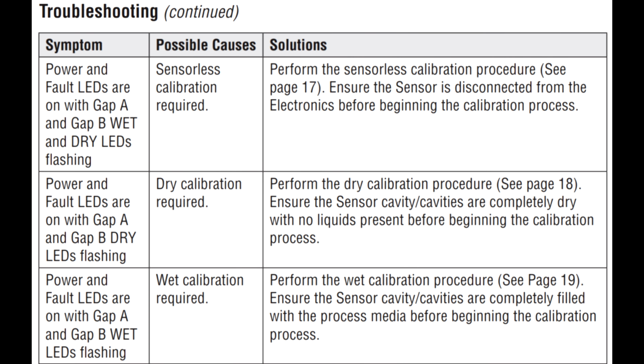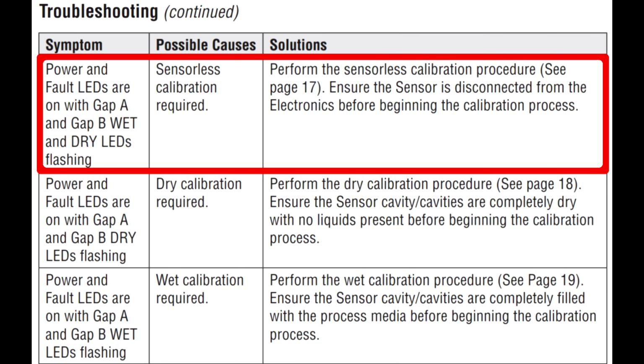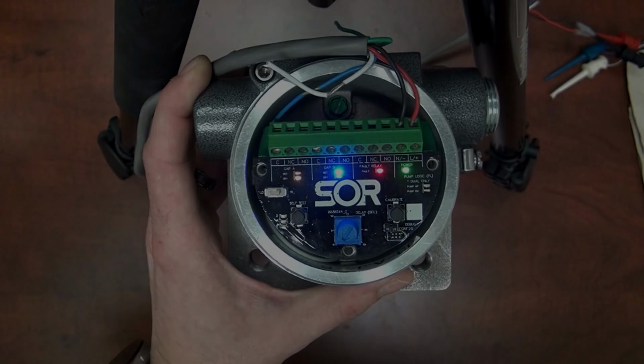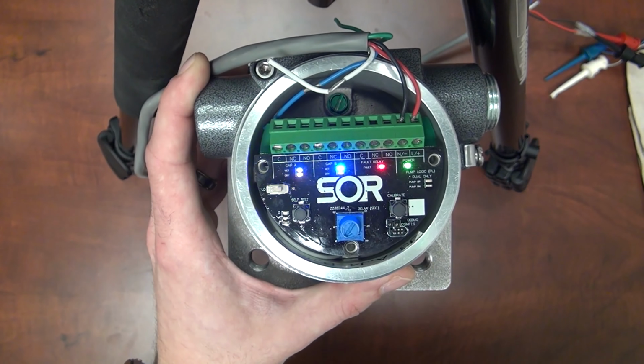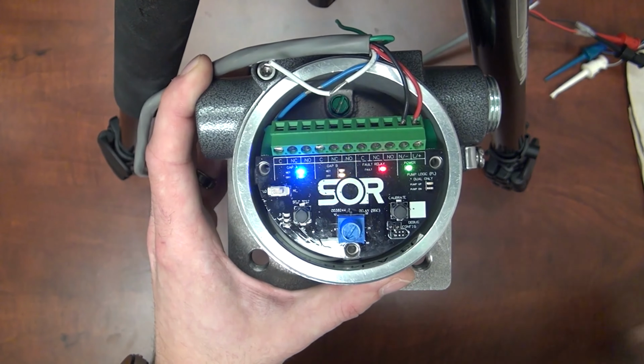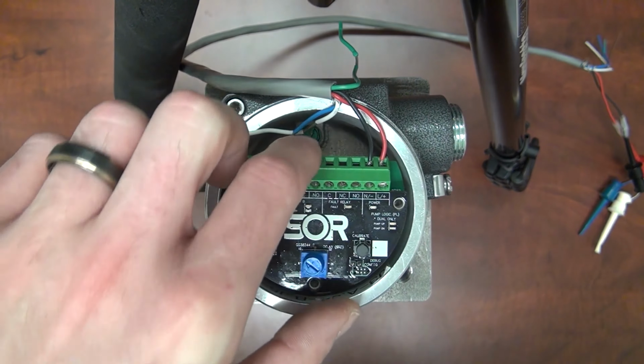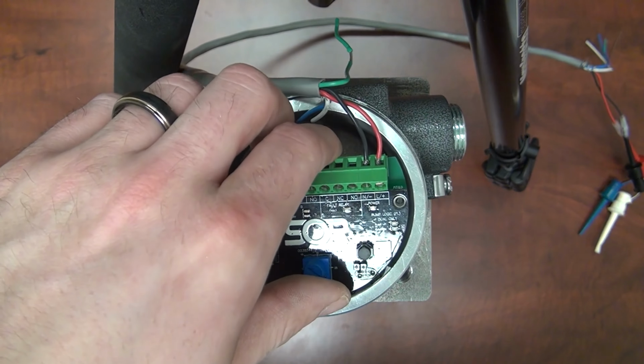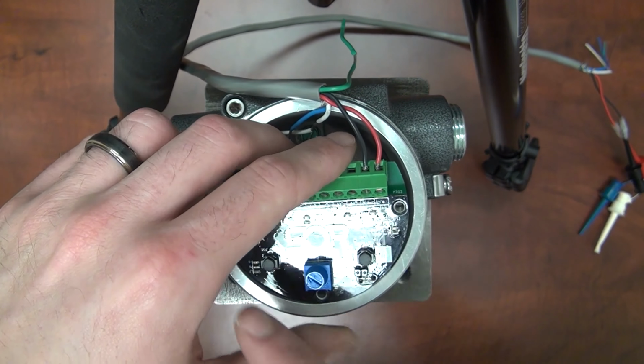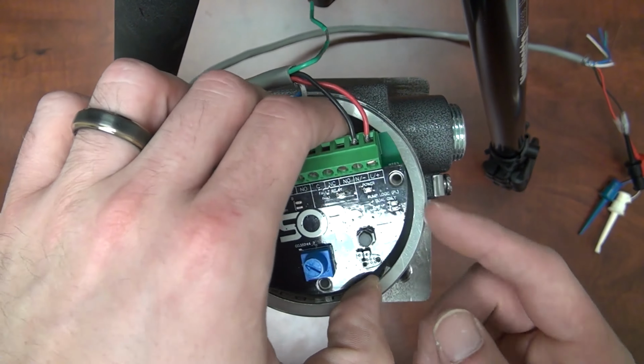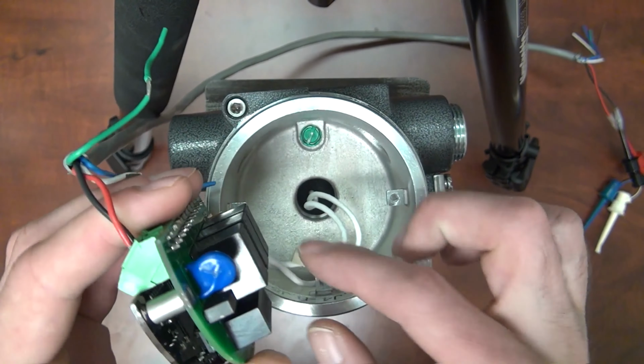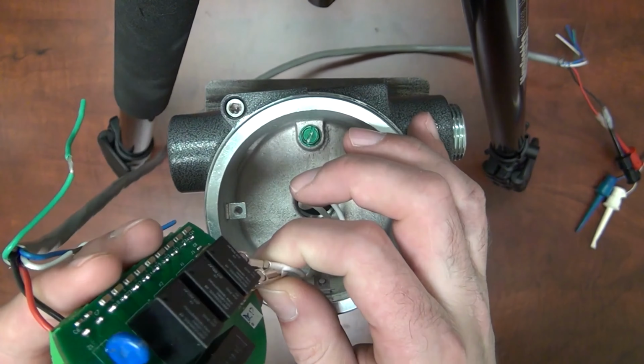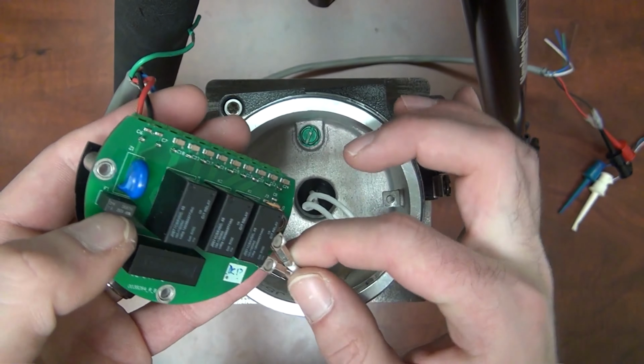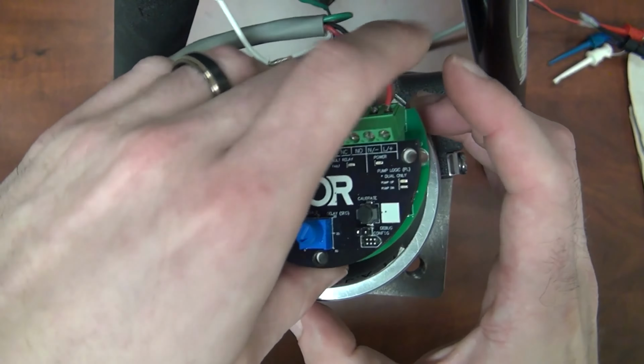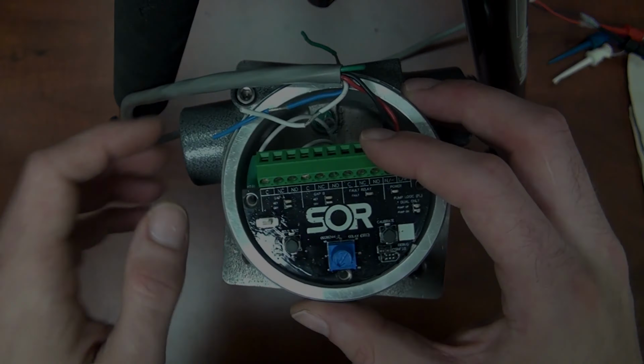If we look here in the table of troubleshooting, we can see that this is an indication that a sensorless calibration is required. To perform the sensorless calibration procedure, we'll start by turning off power to the device. Ensure that the sensor is completely disconnected from electronics. To do that, we'll remove our 3 screws, gently pull out the interface board, and disconnect the sensor cables from the back of our power board. And turn the device back on.